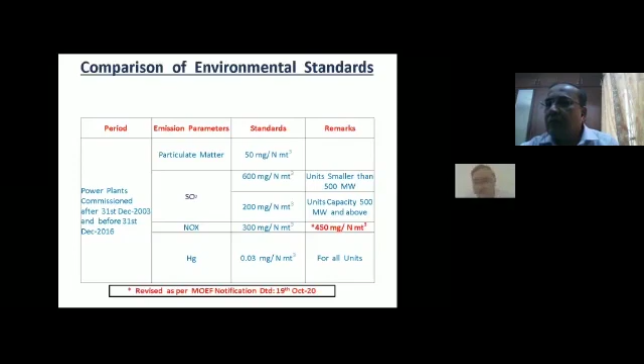And if you go further, the standard says that if the plants are commissioned after 31st December 2003 and before December 2016, which are comparatively newer power plants, particulate matter standards have been drastically reduced. They have to maintain 50 milligram per normal meter cube. The SOx limits are kept at 600 milligram per normal meter cube for small power plants less than 500 megawatt, and 200 milligram per normal meter cube above 500 megawatt. NOx was initially kept at 300 milligram per normal meter cube, which was later increased to 450 milligram per normal meter cube, done very recently, on 19th October. MOEF has revised it, because most of the power plants are just above 300 and below 450. Controlling NOx is a little bit complicated, and it needs a lot of retrofits and a lot of engineering to be done. So most of the power plants commissioned during this period are just crossing 300 and are less than 500.